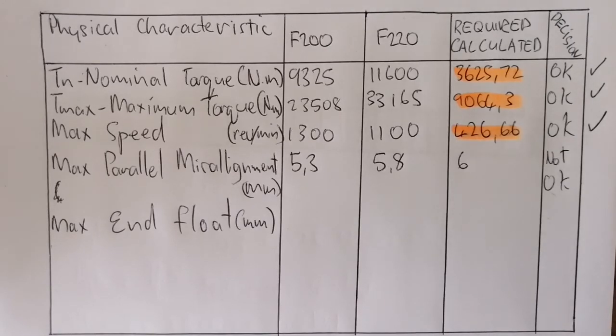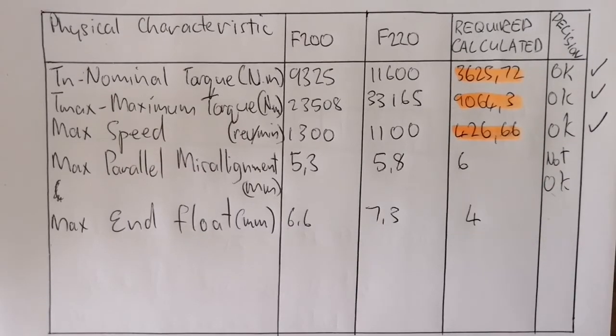Maximum end float - couplings F200 can handle 6.6 millimeters and the F220, 7.3. What we require is 4 millimeters. Therefore it's within spec and it's okay.